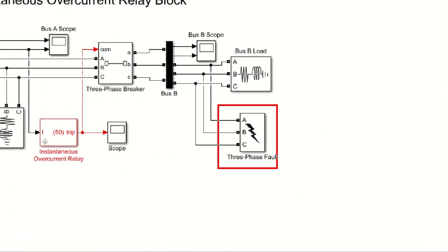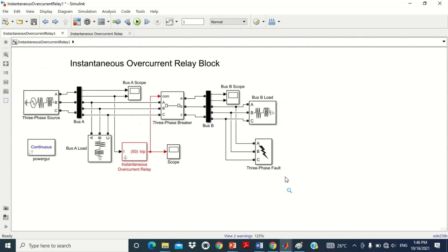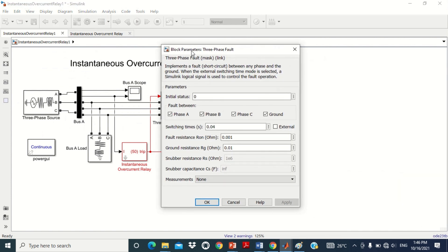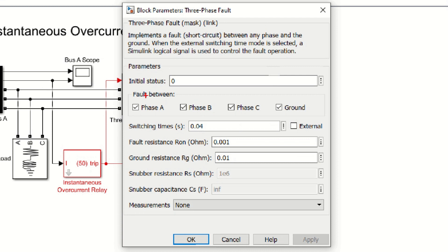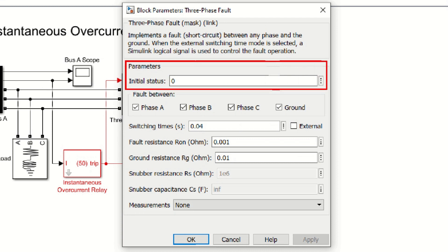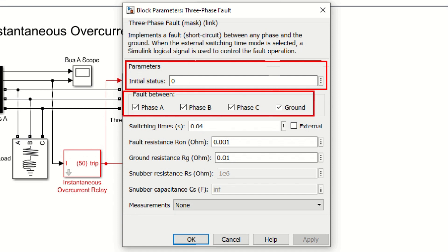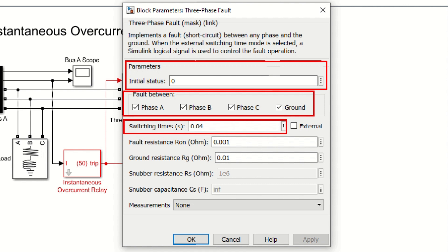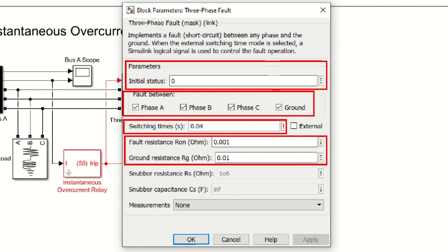Now come to another block of the model — a three-phase fault block connected here to apply a three-phase fault. As we know, in case of a three-phase fault the current increases, so an overcurrent scenario can be simulated using this block. Double click on it to see its values. The initial status is set to 0, meaning the fault is not initially applied. Switching time is set to 0.04 seconds, meaning the fault will be applied at 0.04 seconds. The fault resistance and ground resistance are set to 0.001 and 0.01 ohm respectively.